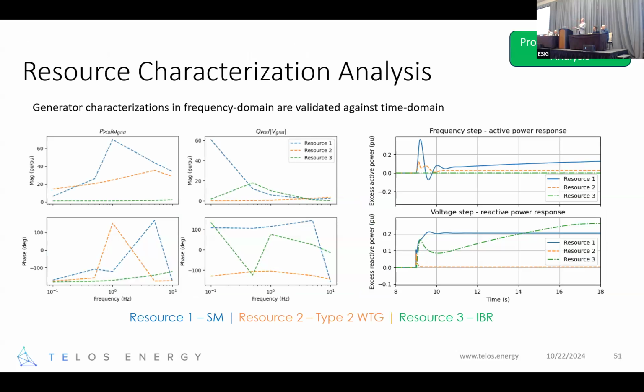The approach we've taken to resource characterization is to look at it in a frequency domain analysis, as well as validate it in a time domain analysis. Going through this quickly, we're looking at perturbations in frequency and checking how much active power is provided in those different timeframes. Similarly, on the reactive power side, a perturbation in voltage and checking how much reactive power is provided by a resource in that response. These plots on the left show the frequency domain view, and on the right the time domain view, to benchmark that.